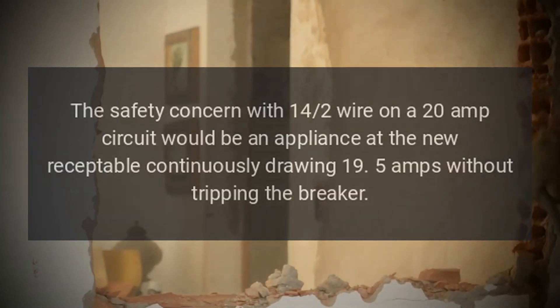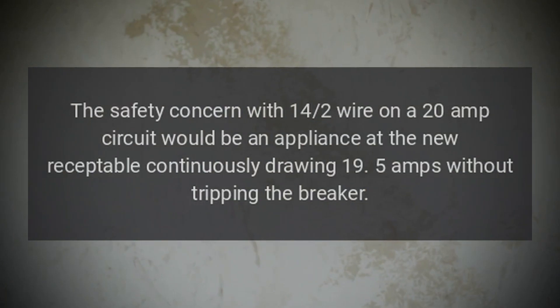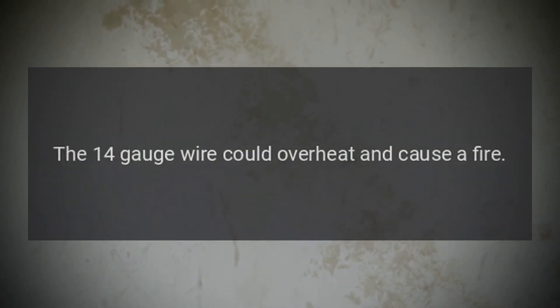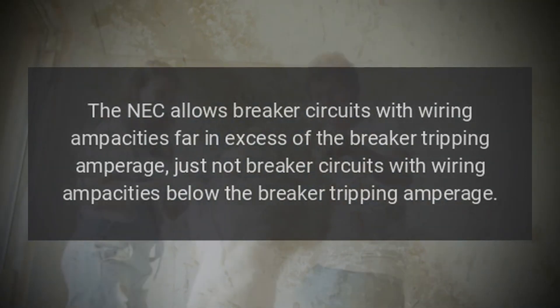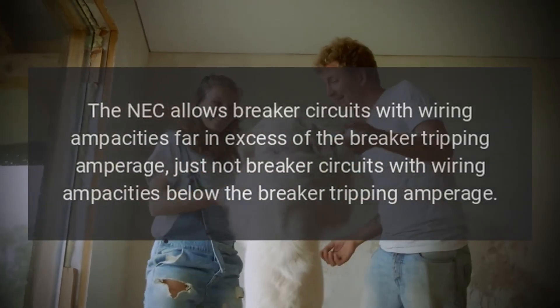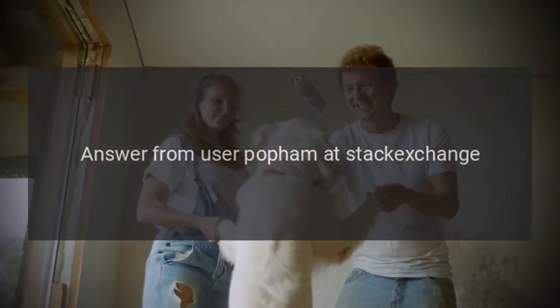The safety concern with 14/2 wire on a 20 amp circuit would be an appliance at the new receptacle continuously drawing 19.5 amps without tripping the breaker — the 14 gauge wire could overheat and cause a fire. The NEC allows breaker circuits with wiring ampacities far in excess of the breaker tripping amperage, just not breaker circuits with wiring ampacities below the breaker tripping amperage. Answer from user Popham at Stack Exchange.